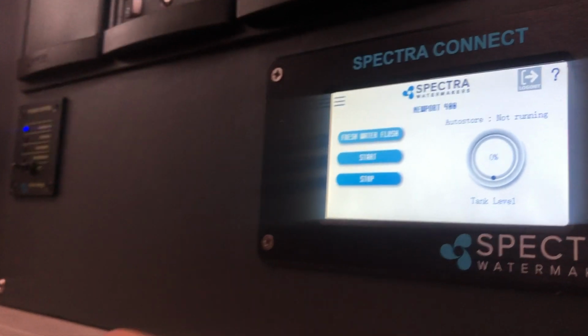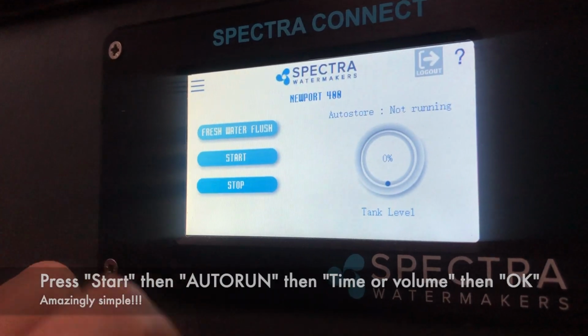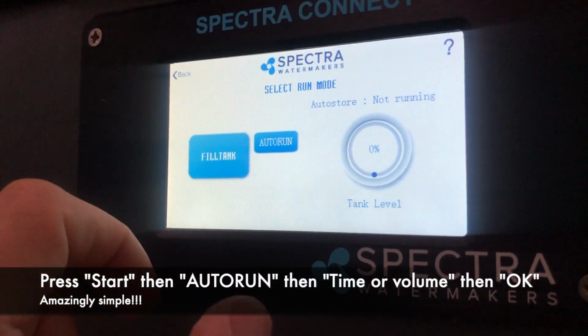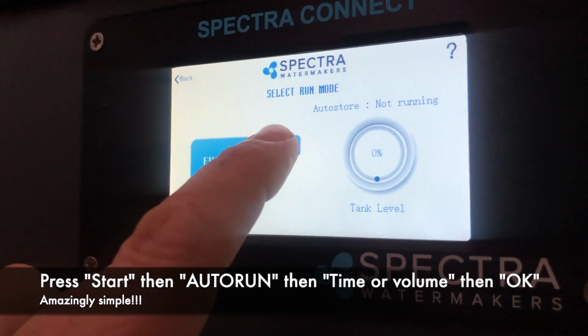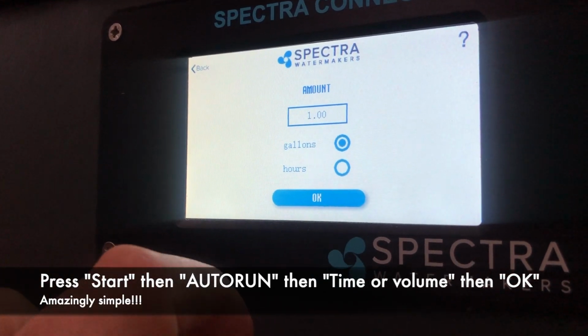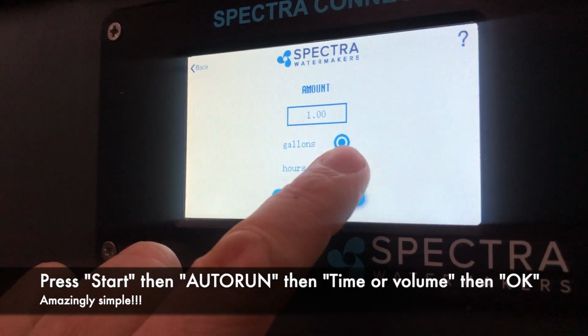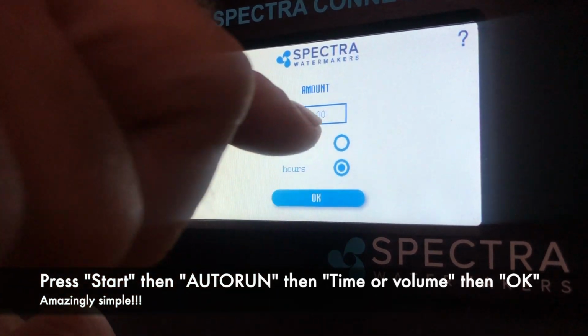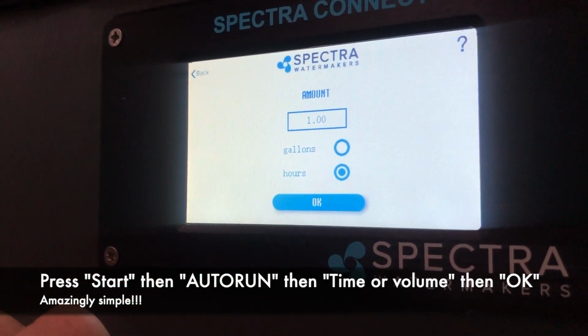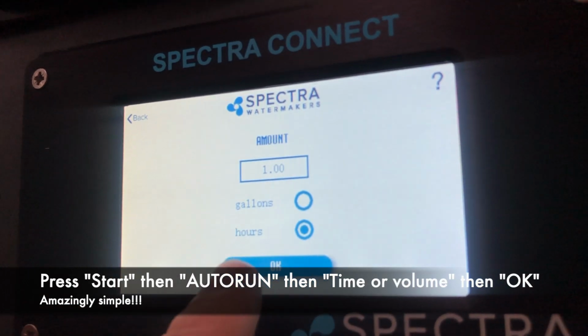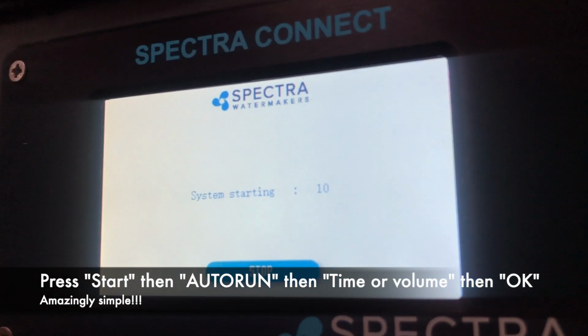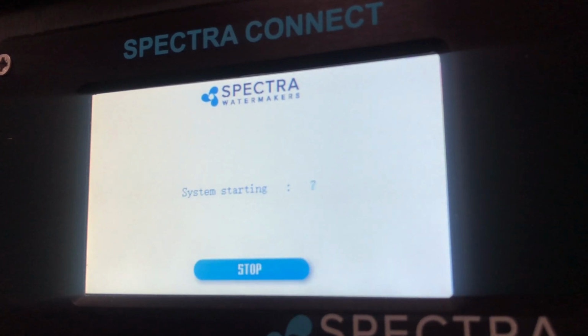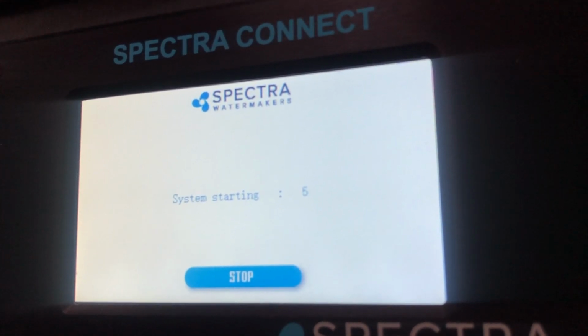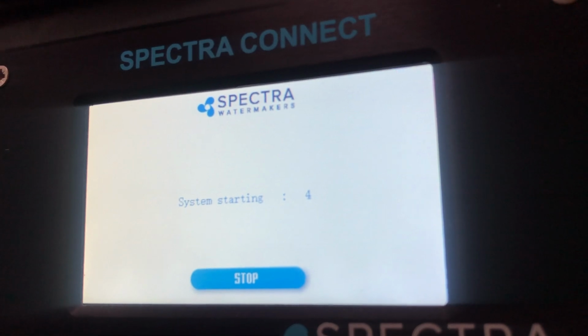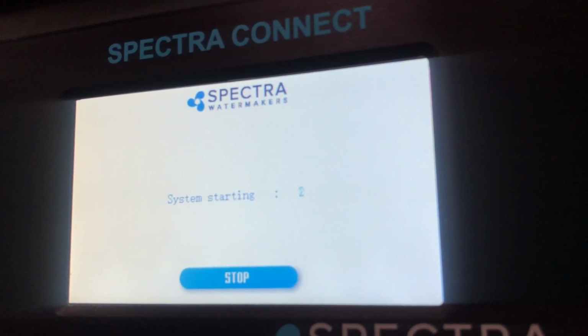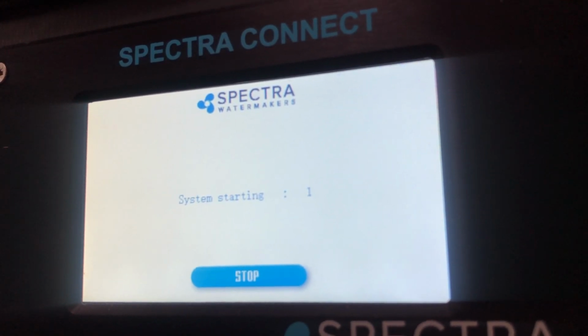You tell me. Okay, you press the start button. Okay, I'm going to get rid of the fill tank eventually, but you want to go to auto run. Okay, and we don't want gallons, we want hours, so press the hours. So it's going to run for 1 hour. Okay. This is where you can program it to run for up to 12 hours. All right, so that'll run for an hour, so hit okay. Okay, system is starting. Now what's happening, it's injecting that fresh water. So if you changed your filters out, it's kind of purging most of the air out of the system. And it'll do that every time it starts.